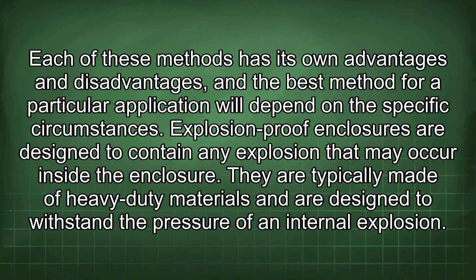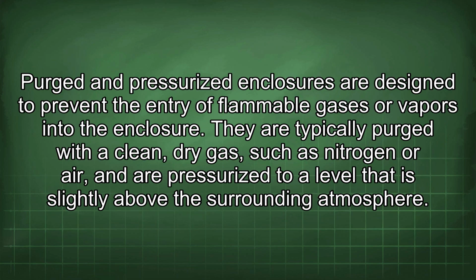Explosion-proof enclosures are designed to contain any explosion that may occur inside the enclosure. They are typically made of heavy-duty materials and are designed to withstand the pressure of an internal explosion. Purged and pressurized enclosures are designed to prevent the entry of flammable gases or vapors into the enclosure. They are typically purged with a clean, dry gas such as nitrogen or air, and are pressurized to a level that is slightly above the surrounding atmosphere.